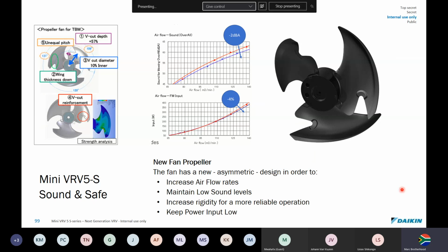Another unique design is this crazy looking fan that Daikin have developed for the VRV5. The weird thing is it's asymmetric design. It's not symmetrical. You can see each blade looks different. This is rather crazy, the way they've done it, because you need to balance this. This is going to tumble terribly without good balancing weights on it. But they've sorted that problem out.